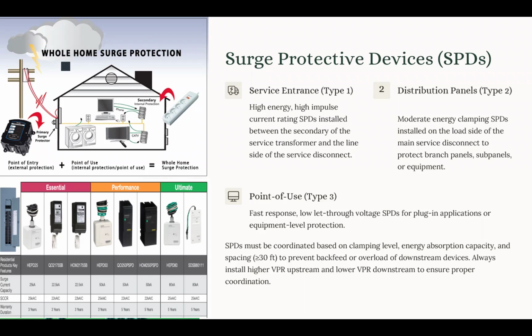We have distribution panel devices, type 2 SPD. They are normally placed on the load side of the main service disconnect, so it is at the distribution panels or sub-panels. The function is intermediate clamping for residual surge that passes through the type 1 or is generated internally by the equipment switching. Now, type 3 is point of use protection, which is basically installed close to the sensitive equipment. It is normally plug-in strips or integrated equipment level modules, and it gives us the final stage clamping to make sure that only low let-through voltages reach the sensitive equipment.